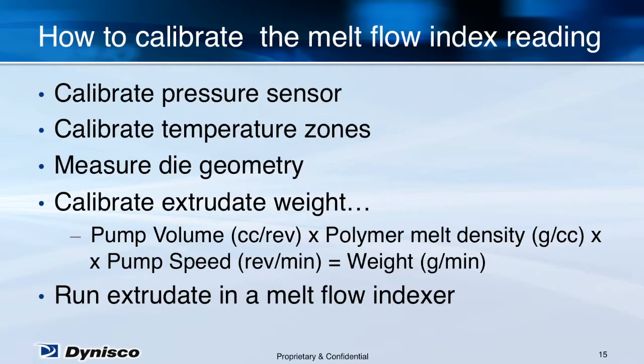The next item to check is the weight of the extrudate. To check the weight calculation, observe what RPM the visco indicator pump is running at while running in MFI mode. Then set the machine up in speed mode and set the RPM to that value. Since this is a bypass rheometer, you can now make a time cut of the extrudate just as you would on a melt flow indexer and verify that the weight matches the expected value based on the pump volume and speed and the polymer density using the formula on the slide.